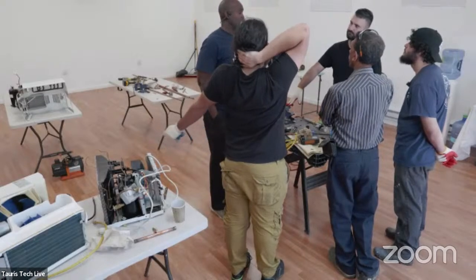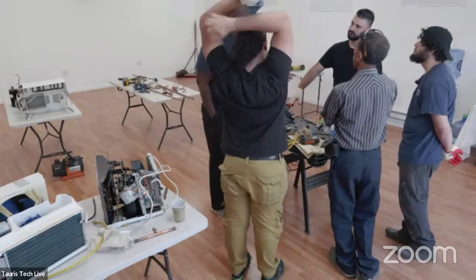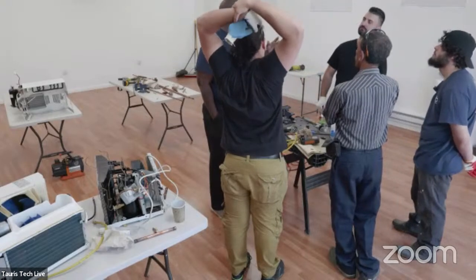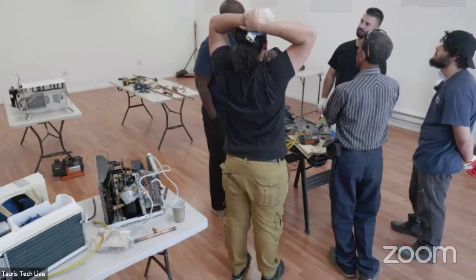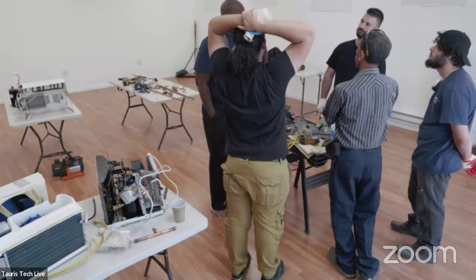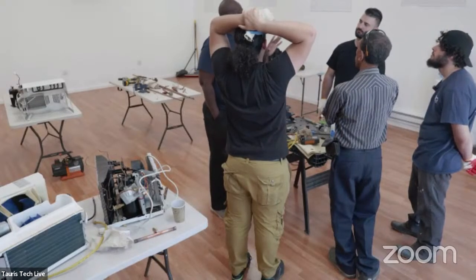So you're supposed to do evacuation after you do the pressure test because you need to remove the moisture. If you don't remove the moisture, it's gonna freeze up inside the machine. So really the 500 microns is about the moisture.